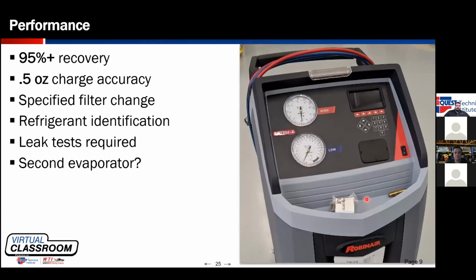As I mentioned, there are leak tests required. After the system is evacuated, before you go to charge the system, you will do a gross vacuum decay leak test. So we'll pull the vacuum, and the machine will sit there and watch for a period of time and see if the vacuum level in the system decays. If it decays past a certain point, we fail the vacuum decay leak test and we will not be allowed to charge.